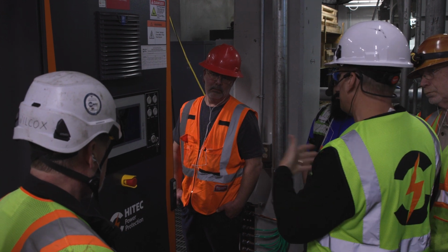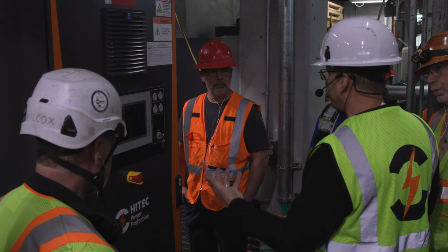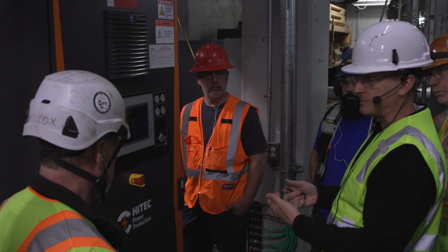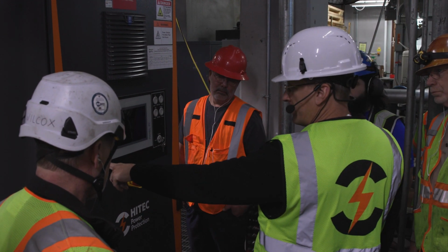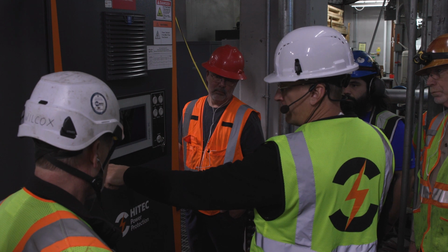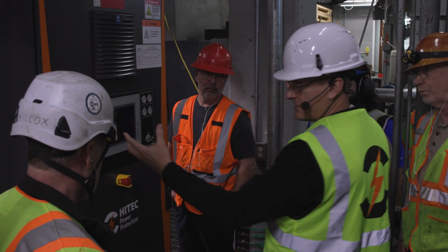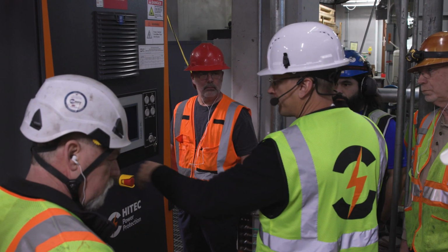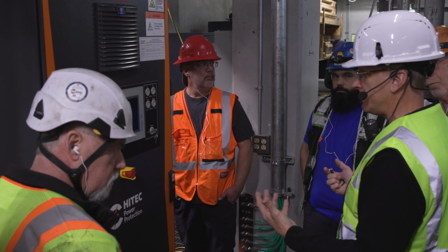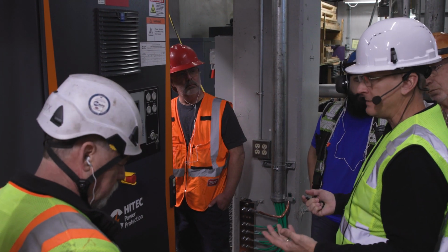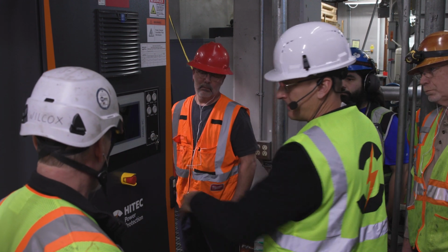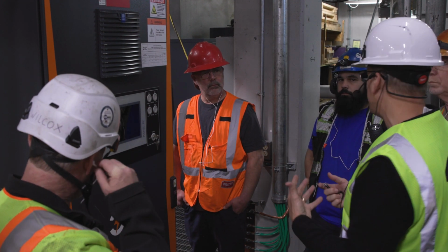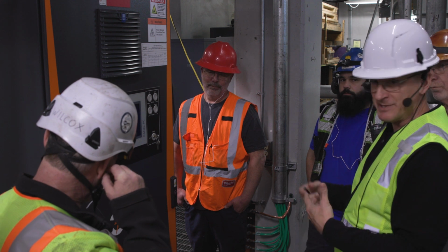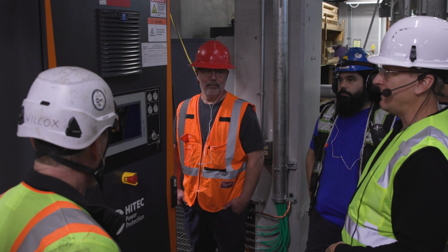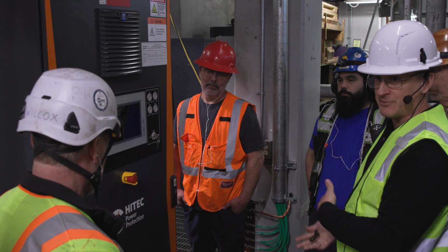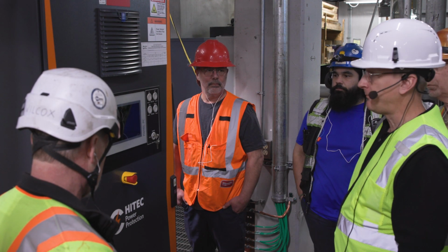We'll go into more detail when we go over the operator's manual to explain what those lights will do. And then of course you've got a lamp test and a buzzer off. This is a button as well, where you can test your light indications. And anytime you get a warning or alarm of any kind, you're also going to get a buzzer. A buzzer will sound. Now of course you're probably not going to hear it because of the noise in the space, but if this were in a separate electrical room, you would certainly hear a buzzer as well.